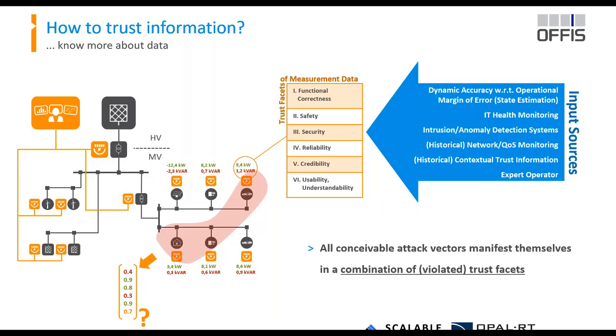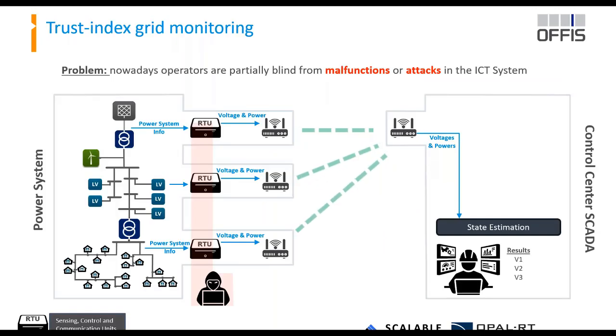To test this, before I go to the next slide which shows the problem, let's look at the current status of the system. You have the power system, and you have some communication devices or measuring devices, control devices, IED, RTU, whatever you call it. Then you have the communication network. The information, mostly voltage and power, or the power system measurement data, goes to the SCADA system.